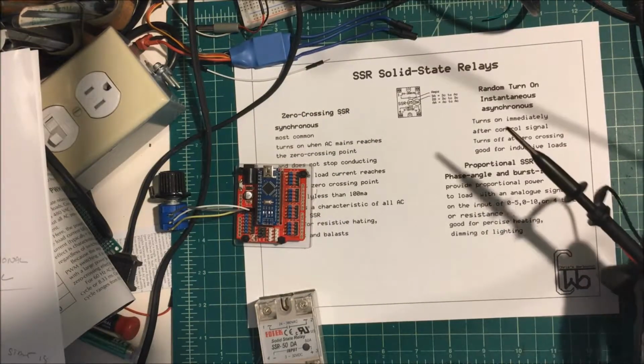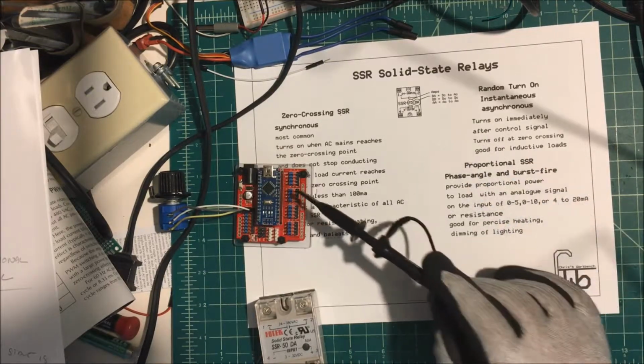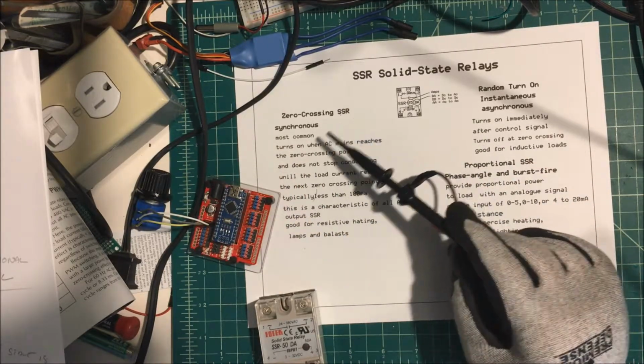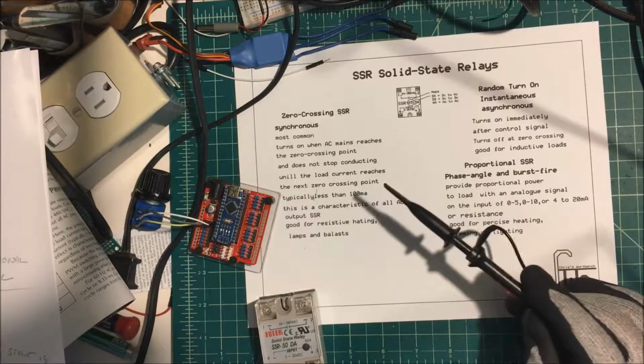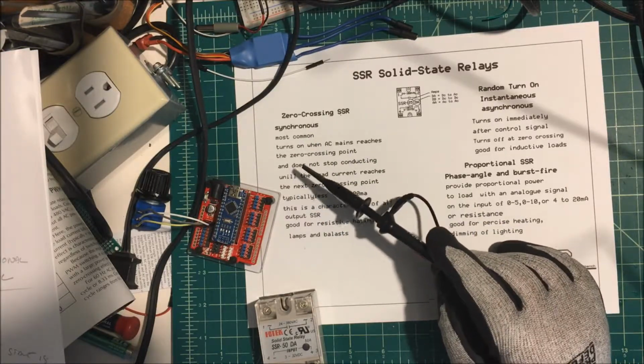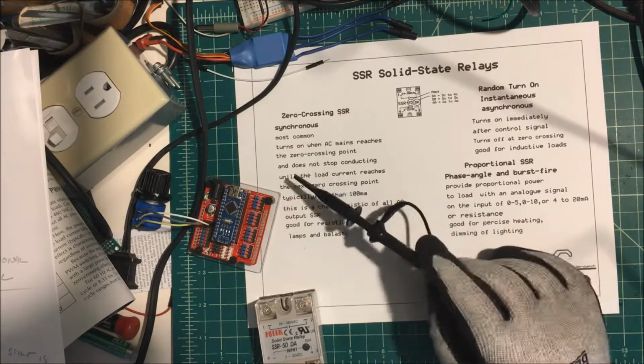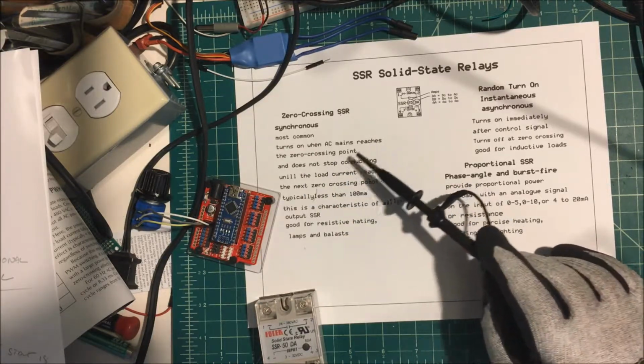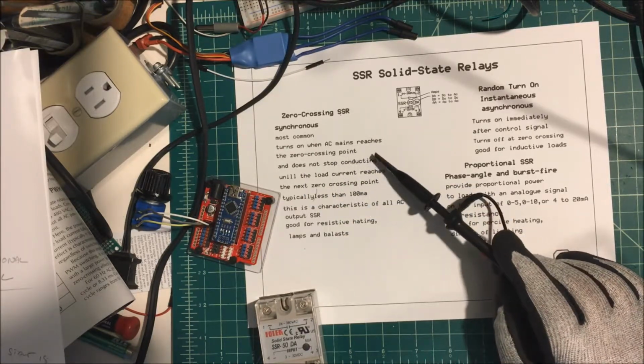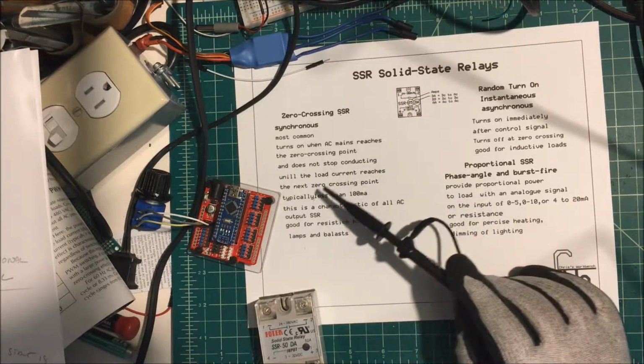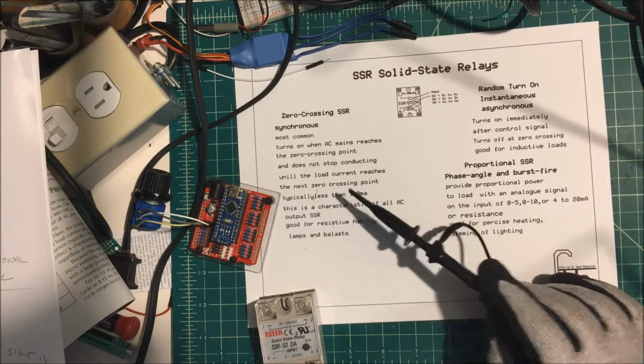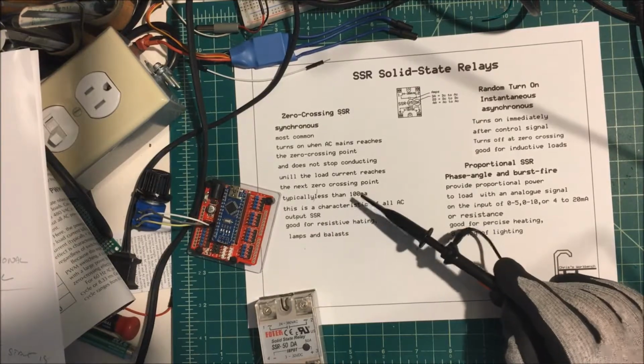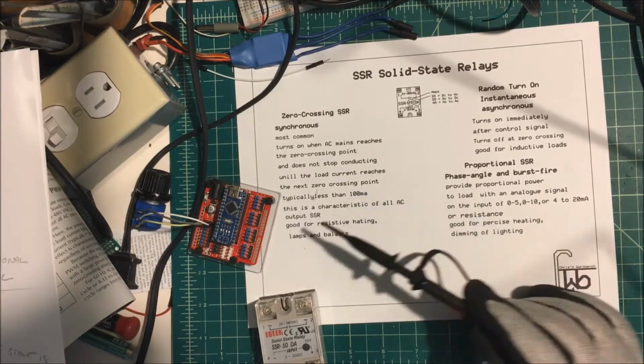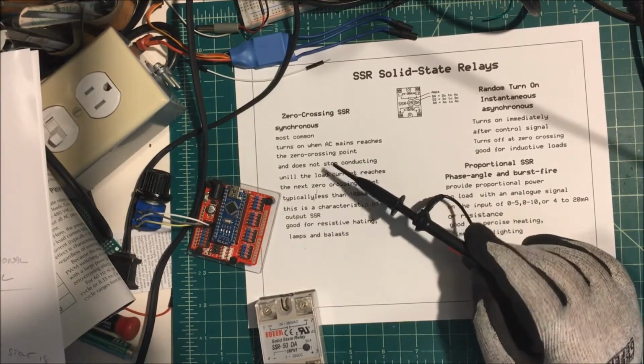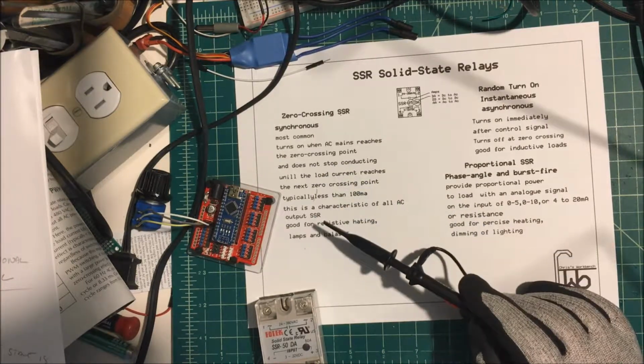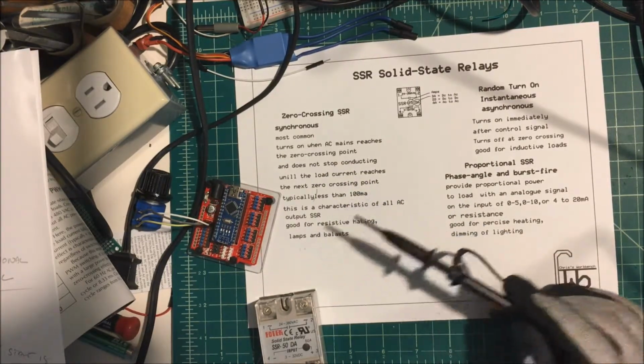Hi, let's talk about SSR solid-state relays. Let's start with a zero-crossing SSR, or synchronous, and they're the most common. When you apply voltage to the input, the output only turns on when the sine wave reaches its zero point. They don't stop conducting until the load reaches the next zero point or drops below 100 milliamps. Because of that, they have good inrush current, and they're good for resistive heating, lamps, ballast, a good general purpose relay.